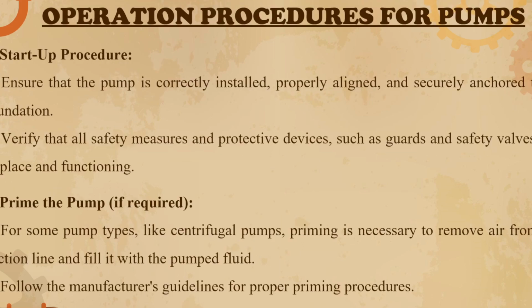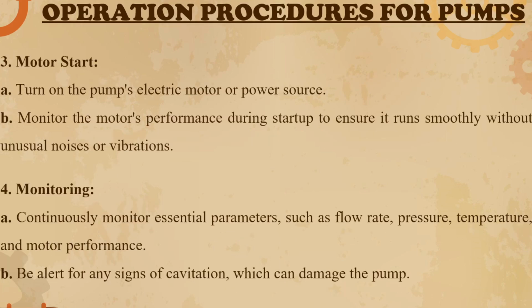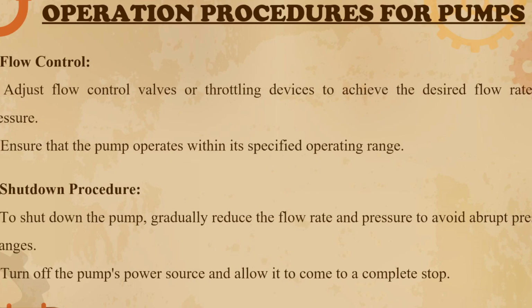Lastly, the last information for pumps is the operation procedure. Same with other machineries, the first procedure is startup procedure. Second is prime the pump if required. For some pump types like centrifugal pumps, priming is necessary to remove air from the suction line and fill it with the pump fluid. Third is the motor start. Fourth procedure is monitoring. Fifth is flow control. Adjust flow control valves or throttling devices to achieve the desired flow rate and pressure. Ensure that the pump operates within its specified operating range.